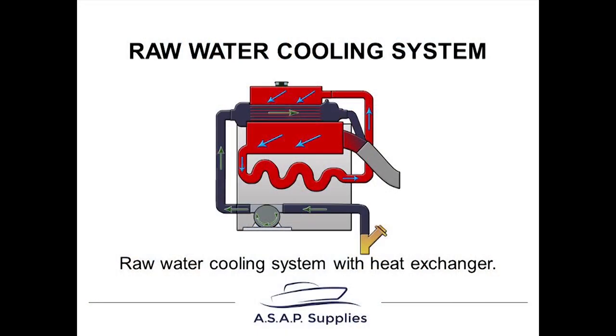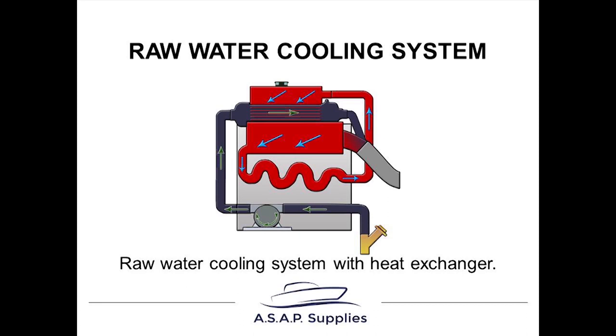Now we've got the engine cooling. This shows a typical raw water cooling system, also called an indirect or freshwater system. You've got two separate circuits separated by the heat exchanger. The fresh water, where you put your antifreeze and coolant inhibitors, goes in at the top in the red system, and that's circulated one way by an engine circulation pump. Then you've got the raw water, which is sucked up from the sea or river depending where you are, through the heat exchanger, and then dumped out of the exhaust system.